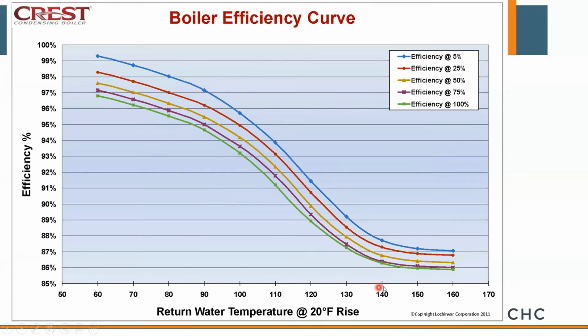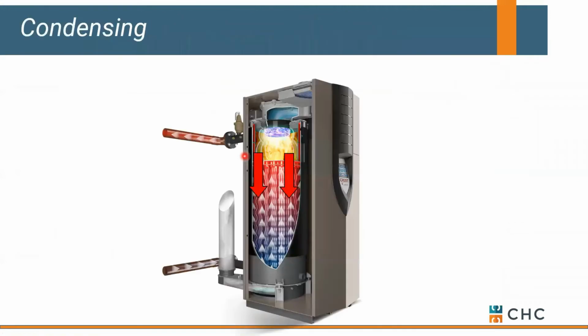More commonly, we're seeing engineers design a system for 140 out and 100 degrees coming back. So instead of a 20 degree, a 40 degree delta T. And that 100 degree return gets us into the mid 90s on our boiler efficiency, trying to improve that efficiency number. Okay, let's talk about what's happening inside the boiler itself, or a fancy heat exchanger.